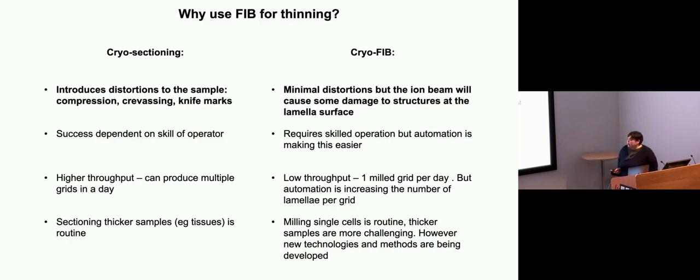Both of these techniques, the success is very much dependent on the skill of the operator. Although with the FIB, the newer technology, there's a lot more automation. It's becoming much more user-friendly. Neither are high throughput, but cryo-sectioning probably wins out. If you're good and know what you're doing, you can produce lots of grids in a single day. Whereas with the cryo-FIB, you're sort of limited to one grid a day, and the number of lamellae depends on whether you're physically sitting in front of the instrument milling or you can run it overnight with automation.